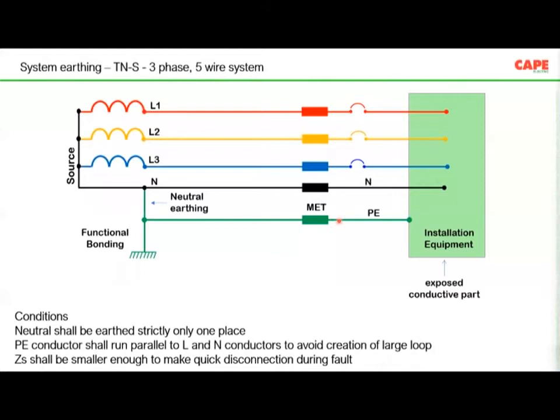Basically, it's a 5-wire system. And the neutral is also earthed, which is a functional bonding. Functional bonding, in the sense that, in order to create a stable voltage in your electrical wires to earth, a functional bonding is created. So basically, this is called a TNS system, meaning a 5-wire system. Neutral shall be strictly earthed only at one place. You are not supposed to connect the neutral at multiple places, then you will have bigger problems. The protective earth conductor, the 5th wire, shall run parallel to the line and the neutral conductor to avoid large loops, and the fault loop impedance of each and every final distribution circuit must be such that the protective device is able to disconnect the supply.